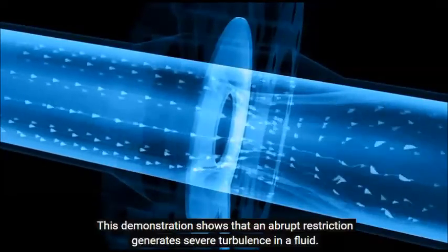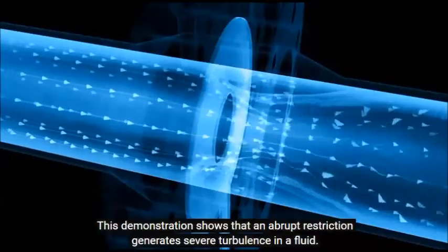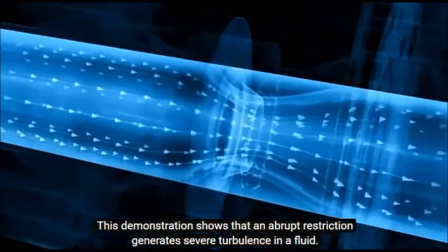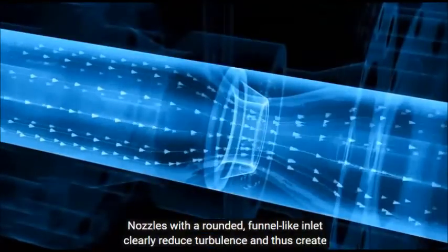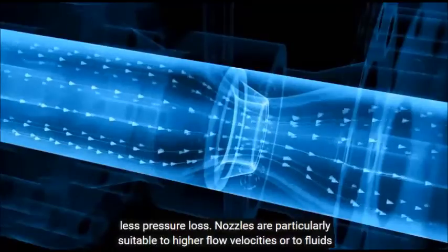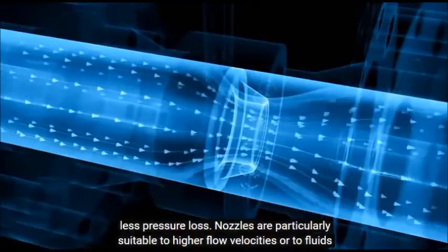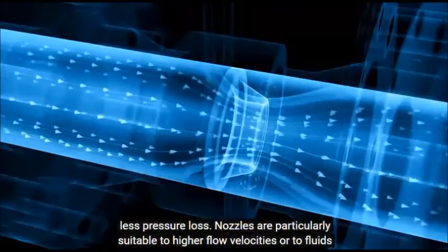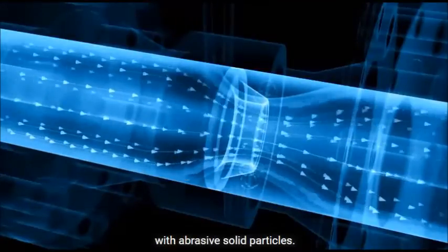This demonstration shows that an abrupt restriction generates severe turbulence in a fluid. Nozzles with a rounded funnel-like inlet clearly reduce turbulence and thus create less pressure loss. Nozzles are particularly suitable to higher flow velocities or to fluids with abrasive solid particles.